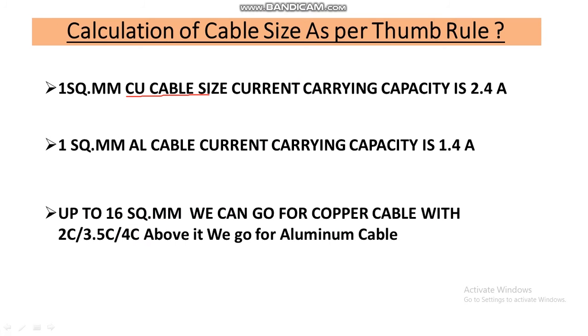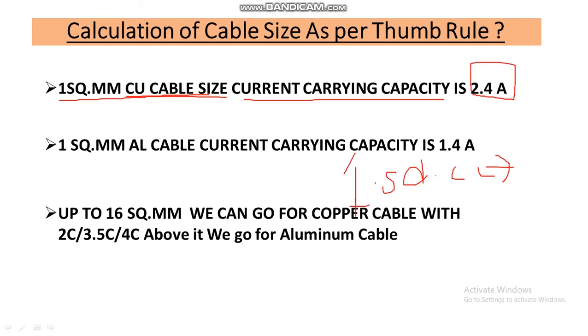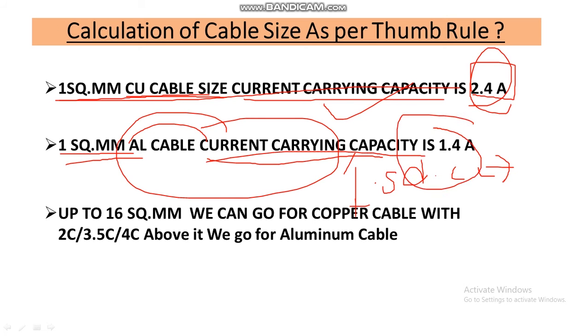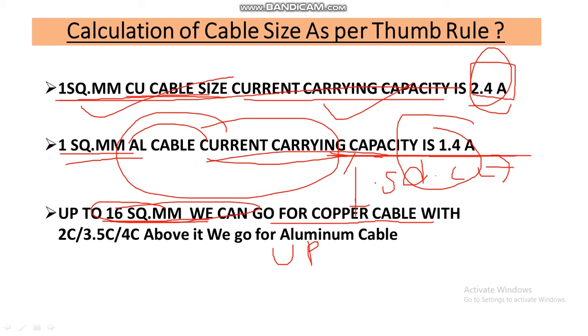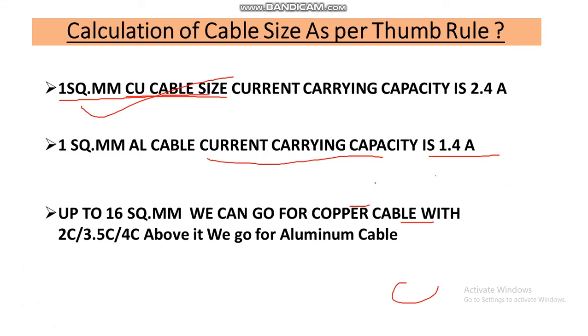For copper cable, one square mm copper cable current carrying capacity is 2.4 amperes. One square mm aluminum cable current carrying capacity is 1.4 amperes. If the calculated cable size is up to 16 square mm, then we go for copper cable. If it is more than 16 square mm, then we go for aluminum cable because of cost saving. These are the thumb rules for calculating the cable size.